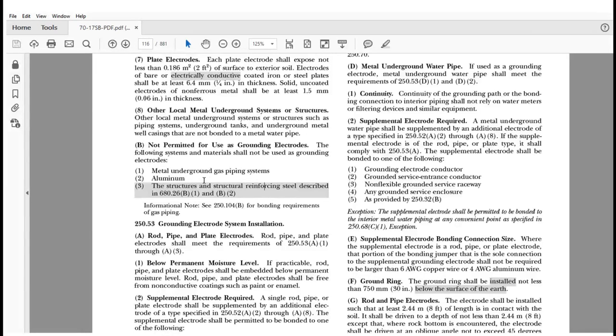All right, so the next one was aluminum. Aluminum is very anti-corrosive. It forms a protective layer. However, we do not have the application where we use it as an electrode in the earth. You can use it as a grounding electrode conductor. You can use it for different types of taps. You can use it for equipment grounding conductors. You can use it as bonding jumpers and different applications, but it is not to be used as an electrode in the earth. Okay? All right, so what was added here?